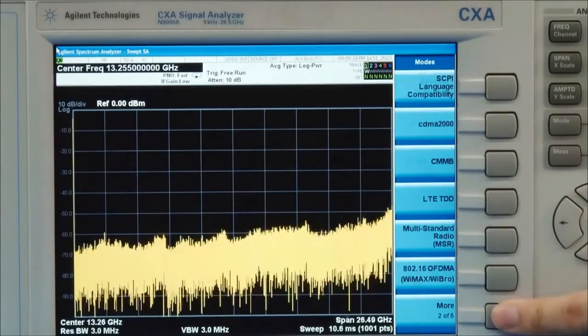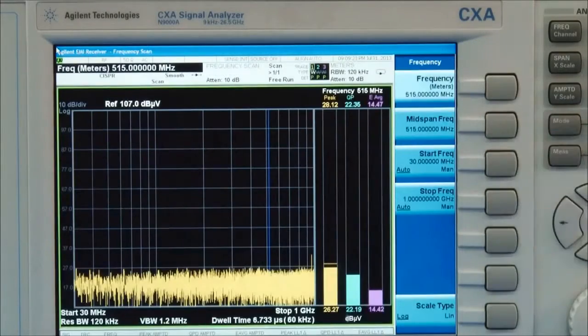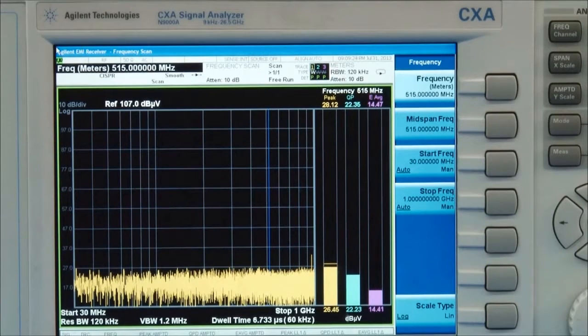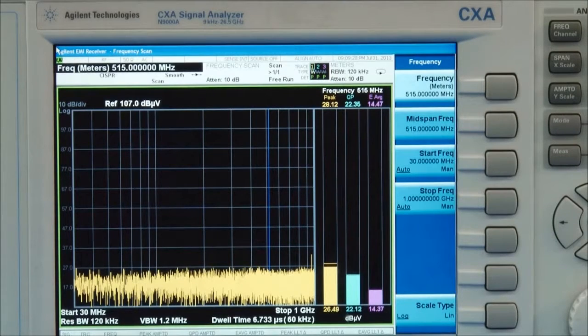When we access the EMI receiver mode, we'll see the display looks different than when the CXA is in normal spectrum analysis mode. In EMI receiver mode, the analyzer is able to make CISPR pre-compliant measurements, which has 6 dB bandwidth filters and selectable EMI detectors, including EMI average, quasi-peak, and peak detectors.